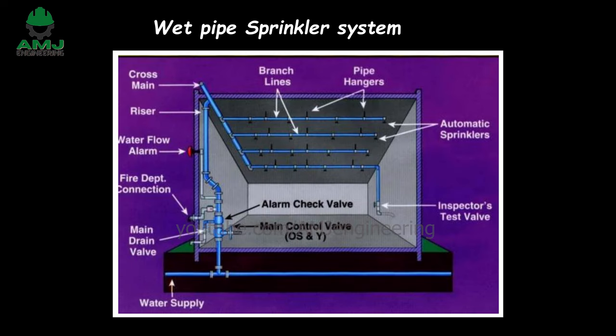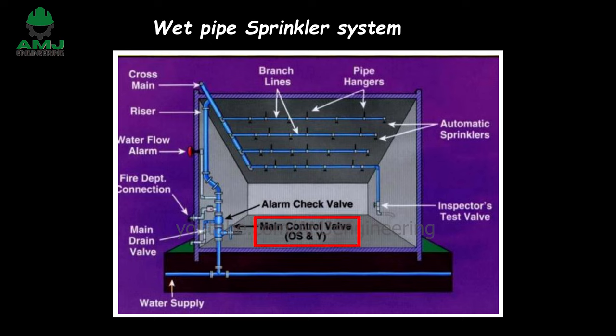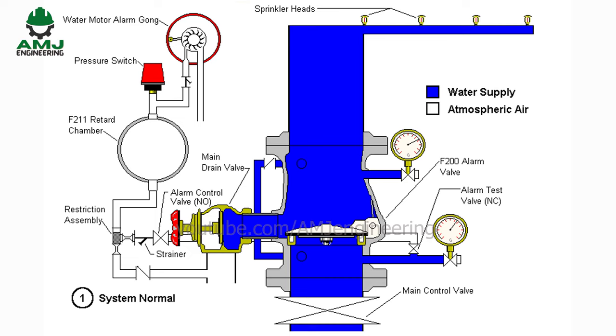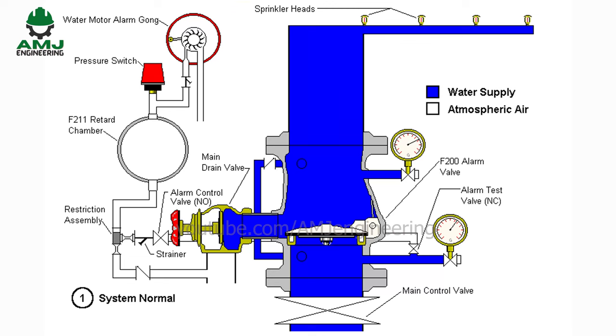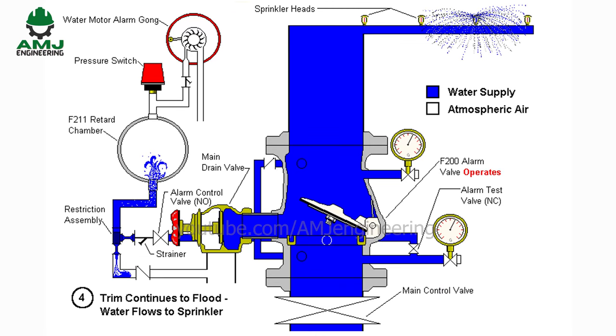Wet pipe sprinkler systems. The components of a wet sprinkler system include, in addition to the water supply, piping, and sprinklers: a backflow prevention device, control valve, main drain, fire department connection, and water flow alarm. Wet pipe sprinkler systems always contain water in the riser and piping. As soon as a sprinkler head activates due to the heat of a fire, water is immediately discharged through the open head.